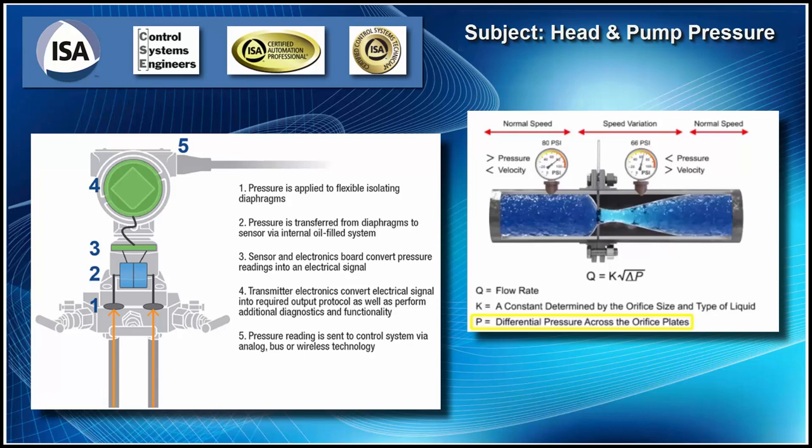So you say, well, the transmitter only measures pressure, and it measures differential pressure. So if you look at this diagram of the transmitter, you'll see there's some little diaphragms down at the bottom. And these diaphragms are connected to a sensor, typically capacitance, and it changes capacitance. Well, we have to do work and apply a force to deflect those diaphragms, and that compresses the fluid above it. Well, we're measuring pressure, and those are calibrated in pounds per square inch for those diaphragms.